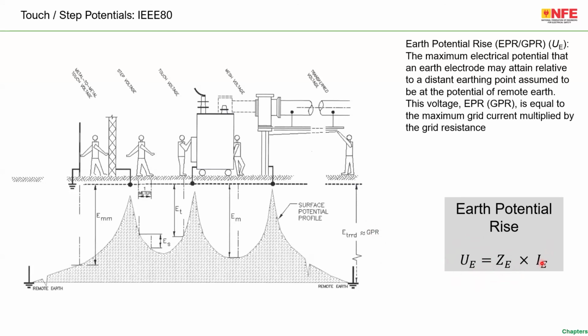Please note that fault current IF is different from IE, because the system has to be designed in such a way that the majority of the fault current returns to the source through some kind of metallic fault return path, for example an earthed conductor, or the shielding or the armoring of a cable. These are there in the regulation. I will show you. As a result, the earth current, the IE, is limited to a low level. As a result, UE is also limited and people are safe. That is the whole phenomenon.